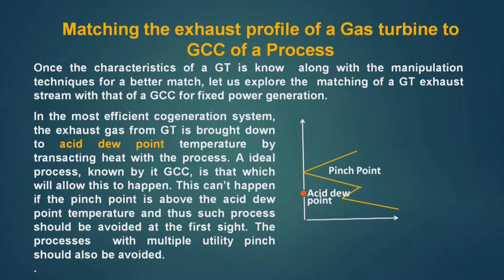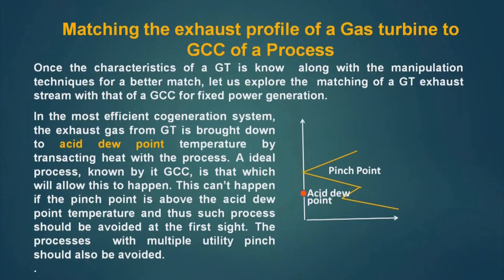The minimum temperature up to which we can go is the acid dew point temperature. In fact, we keep our temperature a little bit higher than the acid dew point temperature in a design, but in an ideal design we can say we can go up to the acid dew point. An ideal process GCC is that which will allow this to happen. However, this cannot happen if the pinch point is above the acid dew point temperature. Here in this plot we see that the acid dew point is below the pinch point, so the GT exhaust gas profile cannot touch the dew point — it has to be above the pinch point.